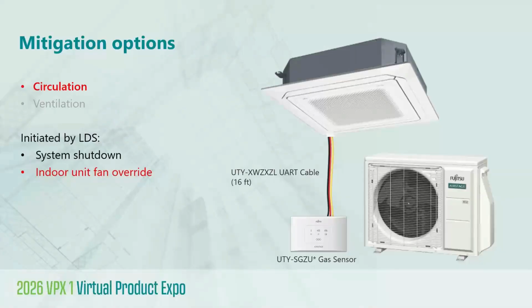So as the name implies, this strategy is strictly just an override of the indoor unit fan. That's it, combined with an immediate system shutdown when a refrigerant concentration threshold is detected. Now, circulation refers to the continued movement of indoor air. So what we're doing is we're helping to disperse or distribute any concentrated refrigerant within a space. And it's really that straightforward. So it's just an indoor unit fan override.